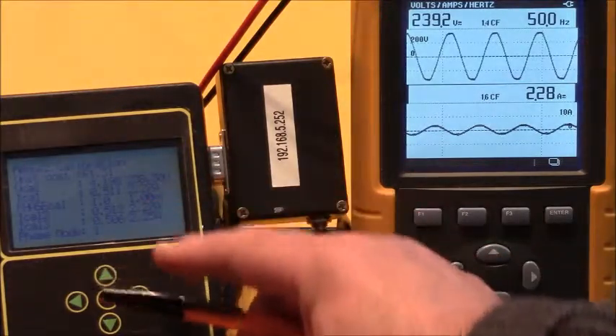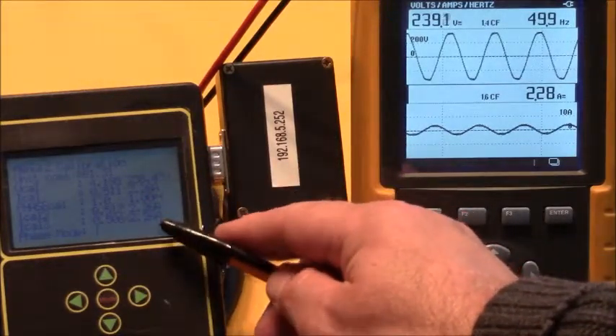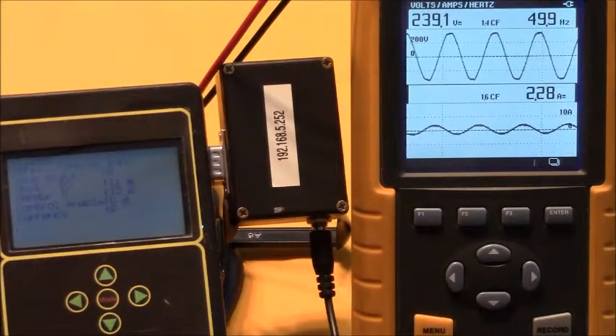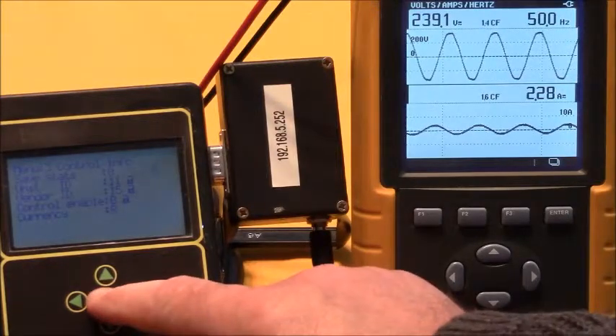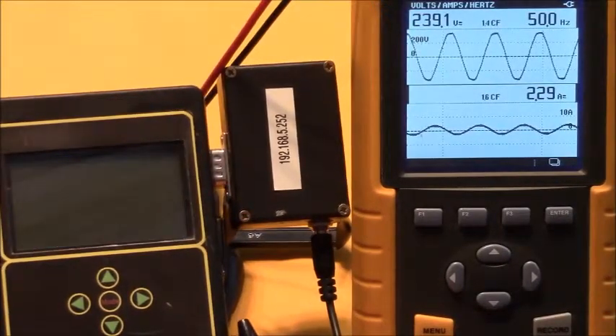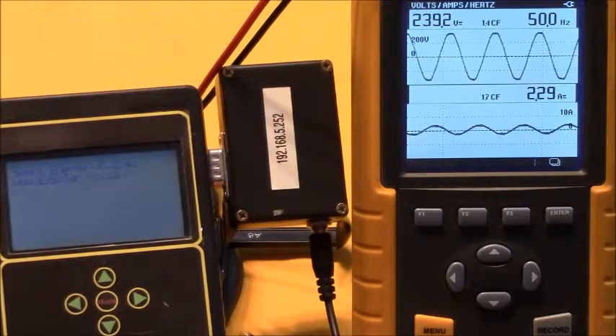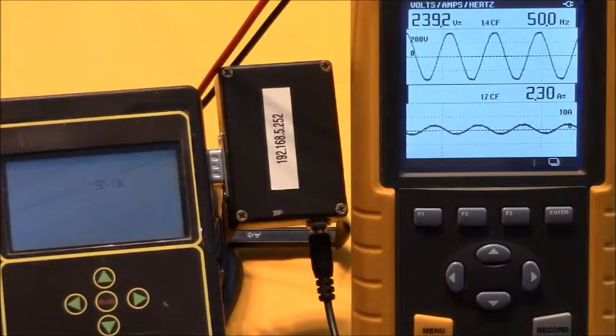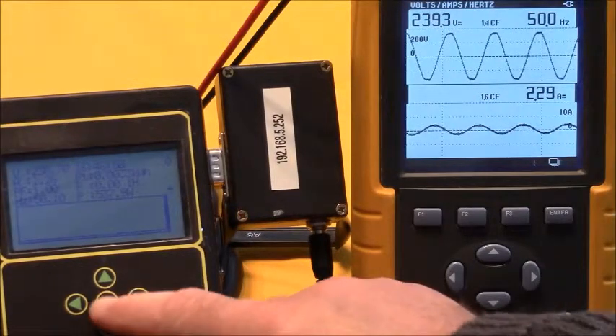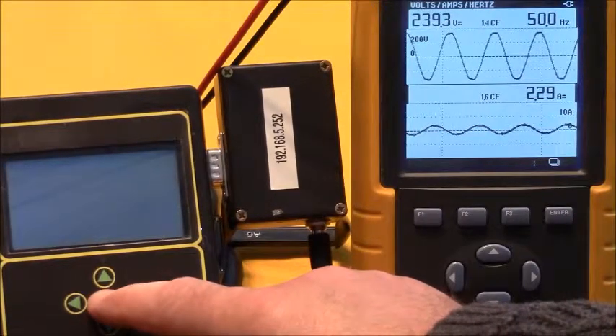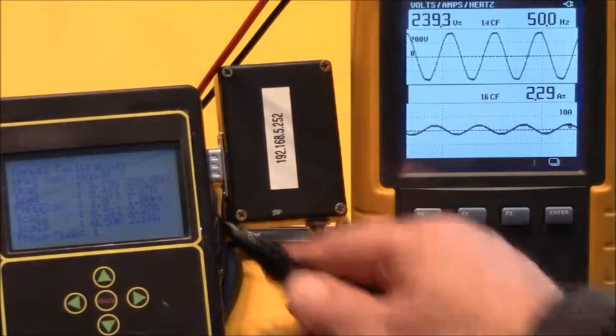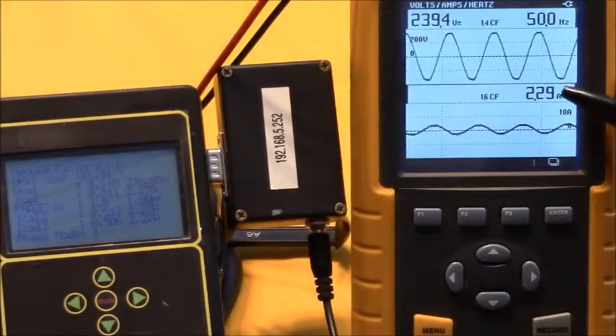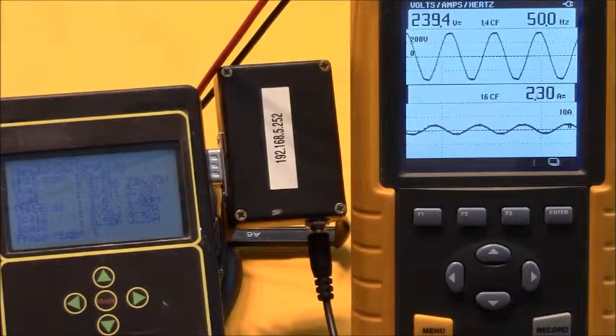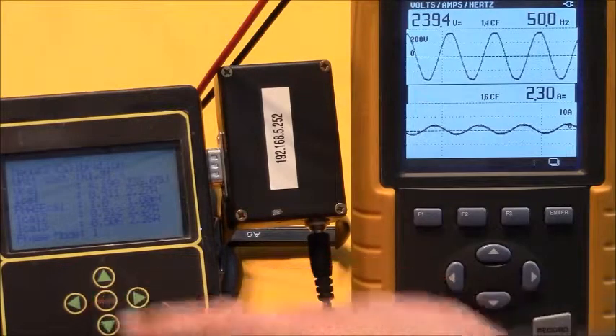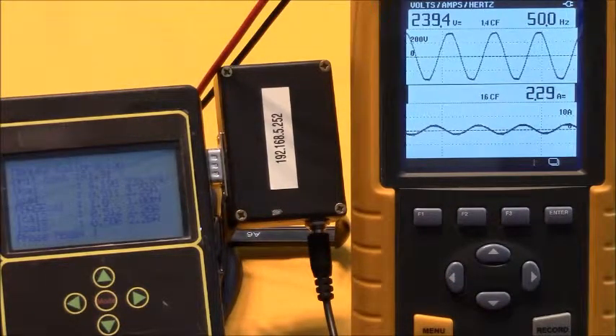And so that's calibrated. One thing to remember again, the values have not been written into the EEPROM until you get out of that screen. Now they've been written into EEPROM. I'll just test that and show you. What we're going to do is reset the unit. And we'll go back into that calibration screen and check the values. 2.27, 2.27, 2.27, this is 2.29 now. It's less than 1% out, which is totally acceptable. And that completes the calibration of the energy monitor from ExSolar.